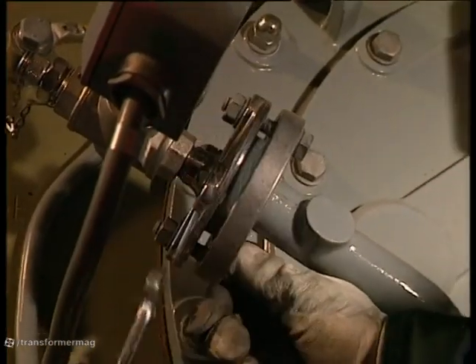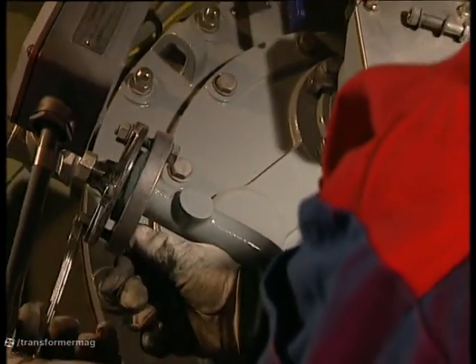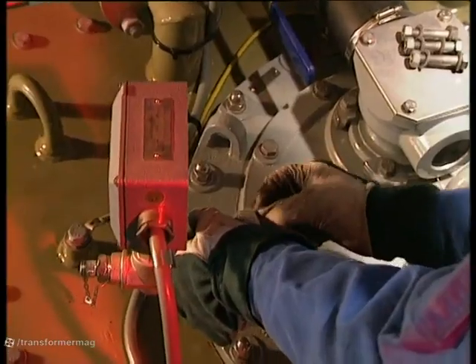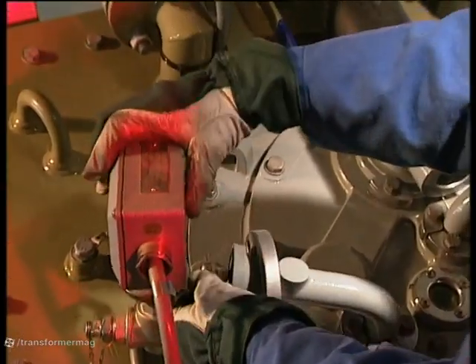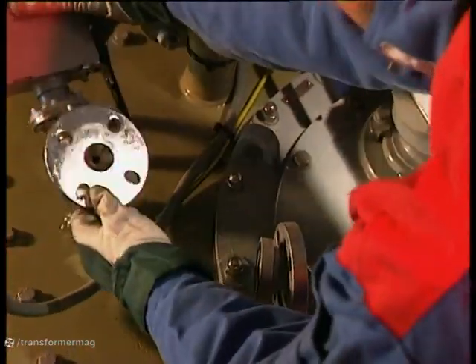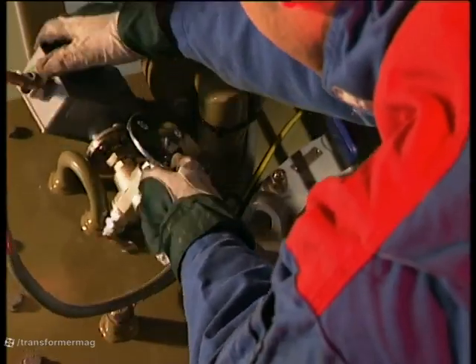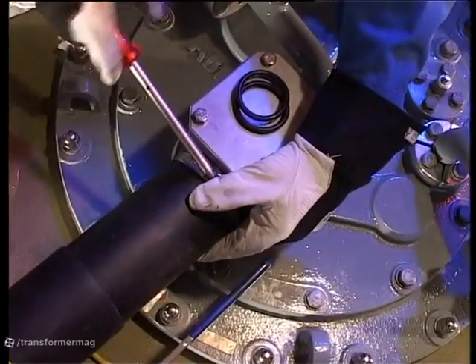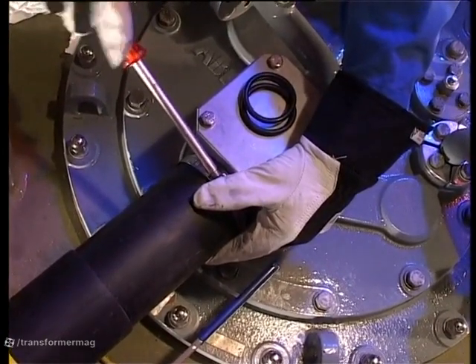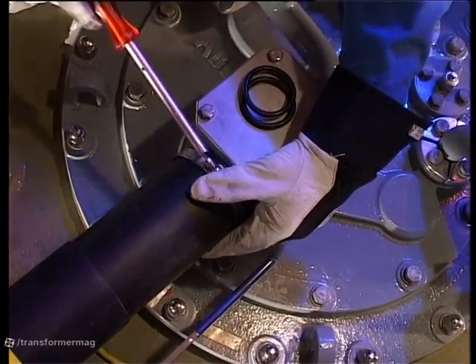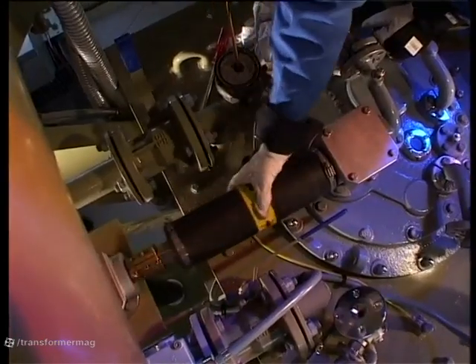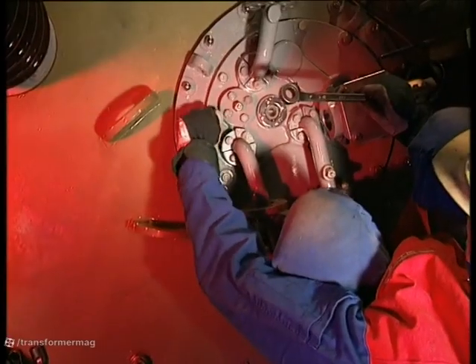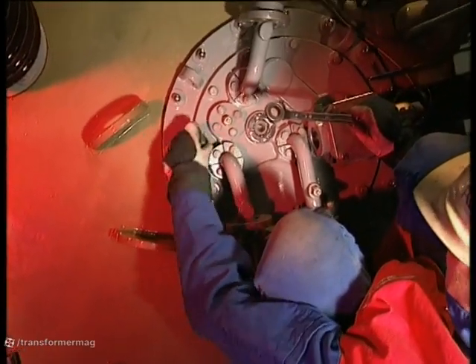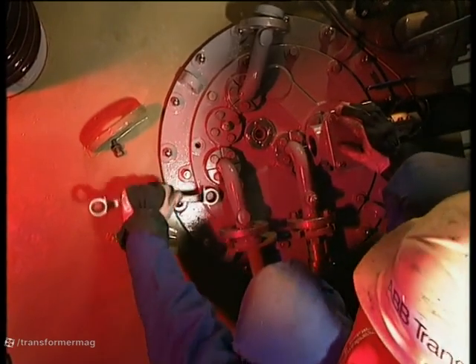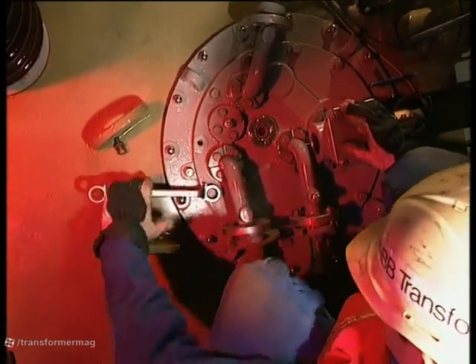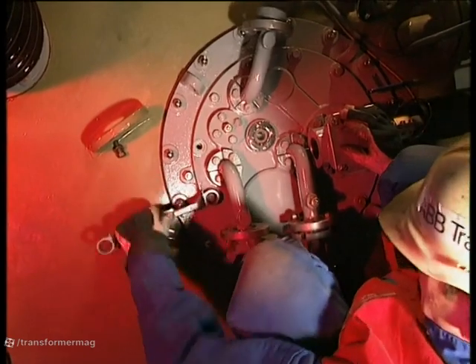Now we'll remove the tap changer cover. Close the valve to the conservator, disconnect the connection and other pipe connections to the cover. Slacken the hose clips that hold the protective tube on the bevel gears and push it together. Unscrew the cover screws. It's a good idea to empty all your pockets so that nothing falls into the tap changer when the cover is off.